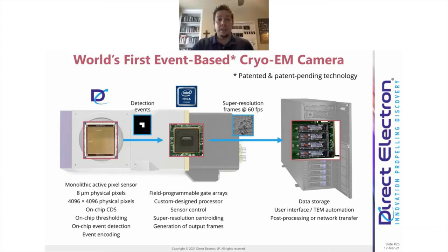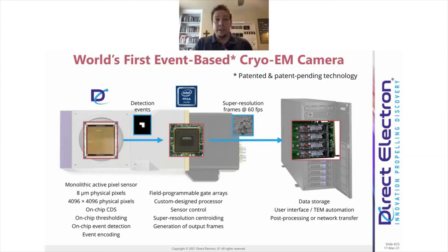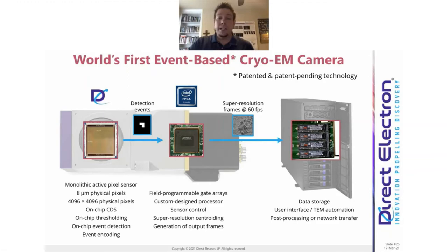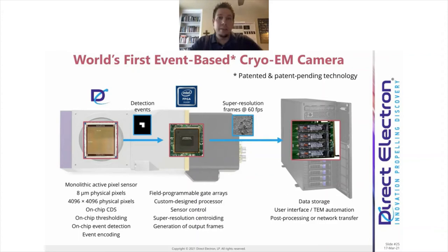These frames look very much like frames from a conventional camera in integrating mode, in that each frame has sufficient contrast to do motion correction. But instead of being integrating mode frames, these are counting frames — the camera is always providing electron counting inherently in hardware. That means the computer is no longer responsible for heavy processing. The computer is simplified to high-speed data storage, dumping data to disk and sending it out over the network; graphics cards can then handle particle picking, motion correction, and CTF estimation.